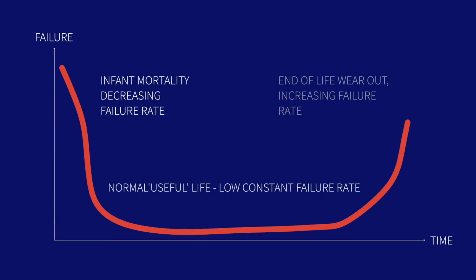The curve describes the relative failure rate of a group of products, such as the entire component makeup of a switch panel, over time. As stated, the useful life of electrical switchgear is normally in the region of 15 to 20 years, and the power installations at many buildings constructed prior to the millennium is of an age which puts them clearly at risk of increased failure on the end-of-life section of the bathtub curve.